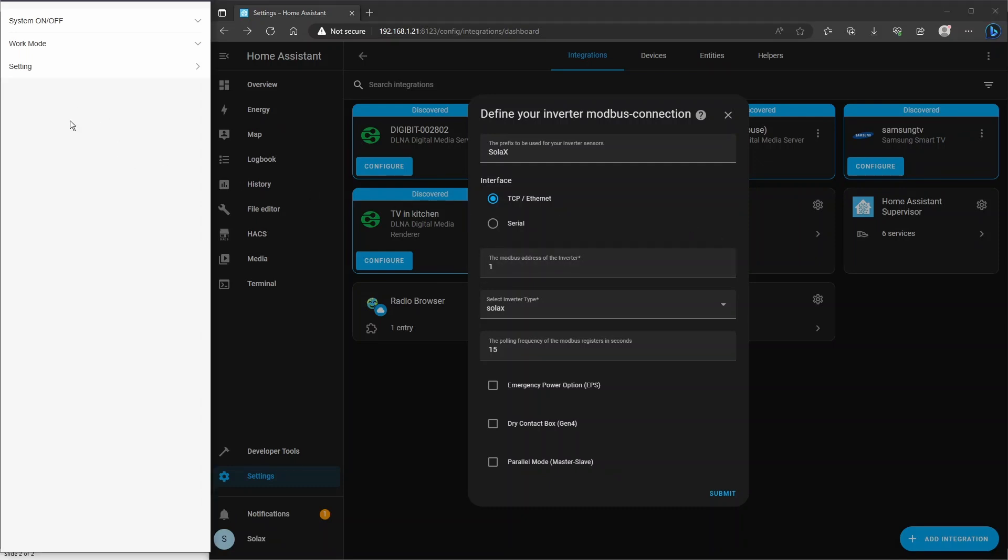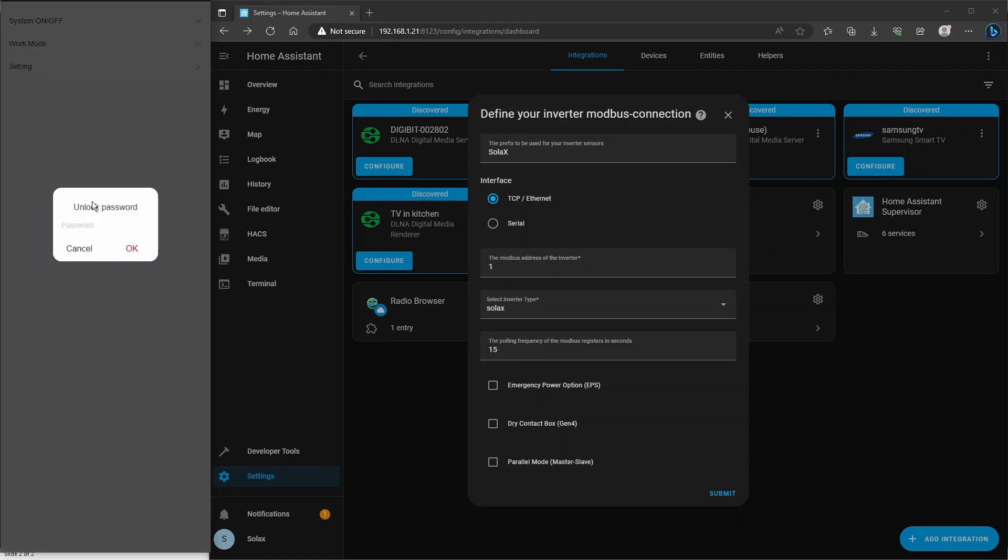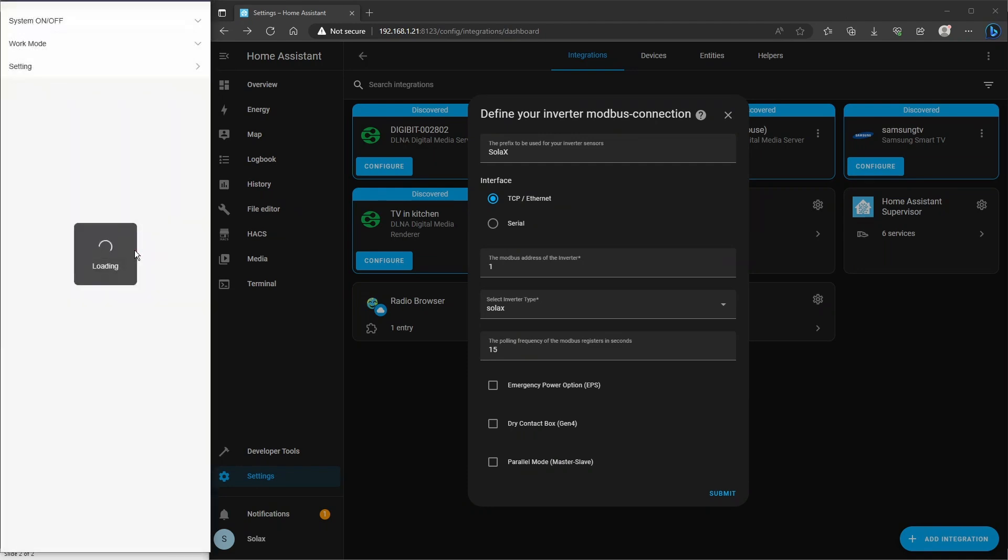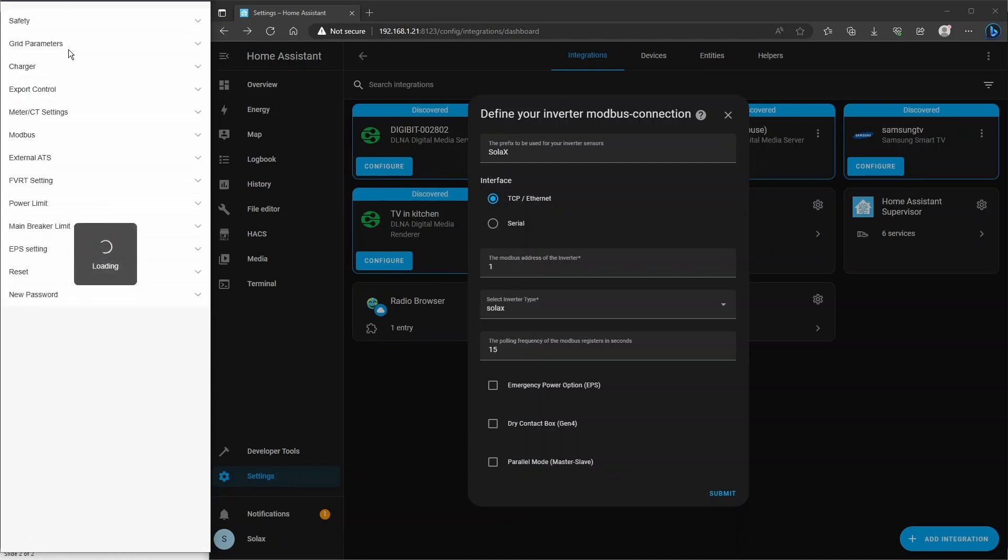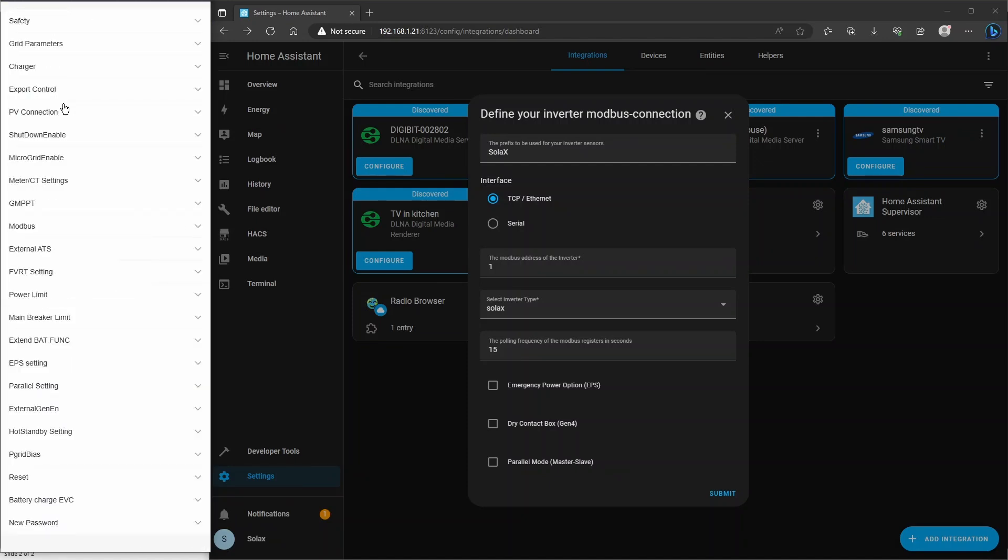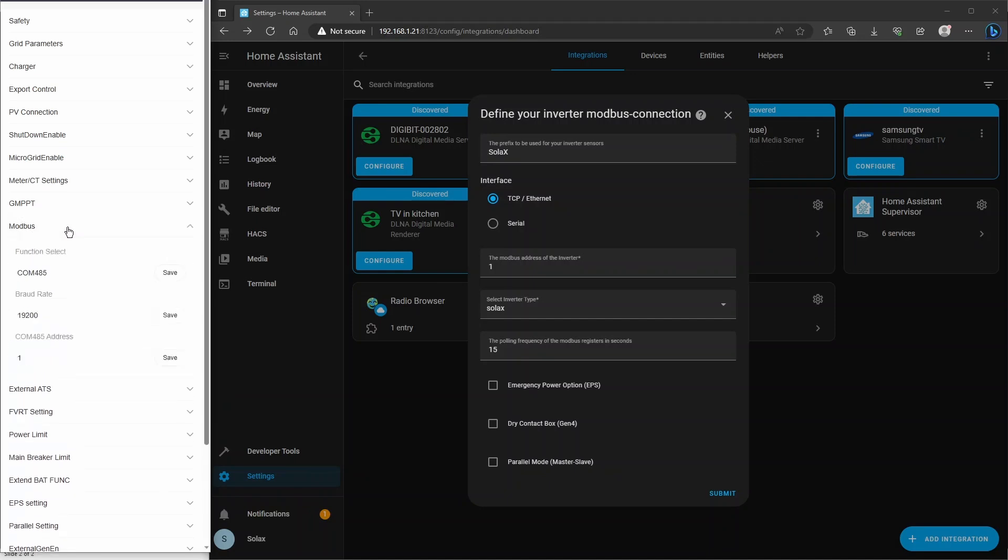So on the left hand side here, go on to the settings of your inverter, and then we're going to type in 2014 for the code number to access the advanced menu. Click on the advanced menu, and scroll down to where it says Modbus in the menu item, and click on that. So you can see it says COM485 for function select, baud rate 19,200, and the address is 1.